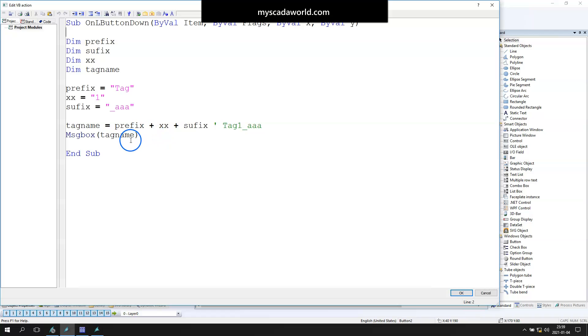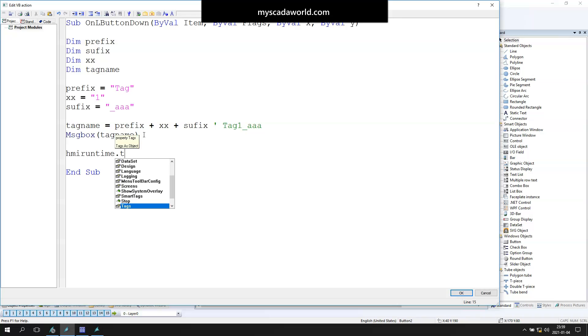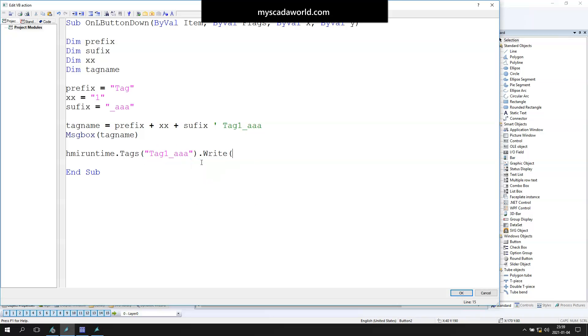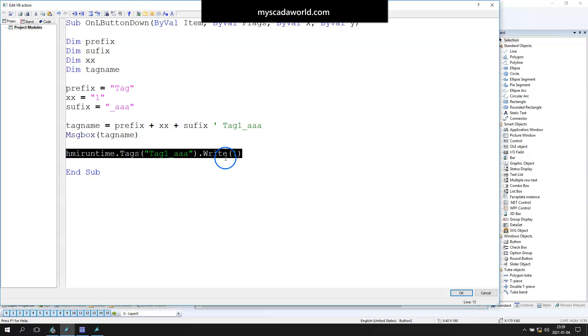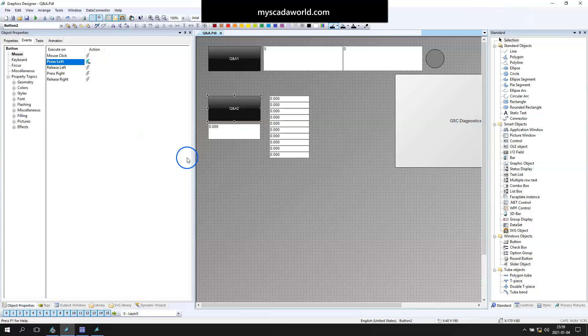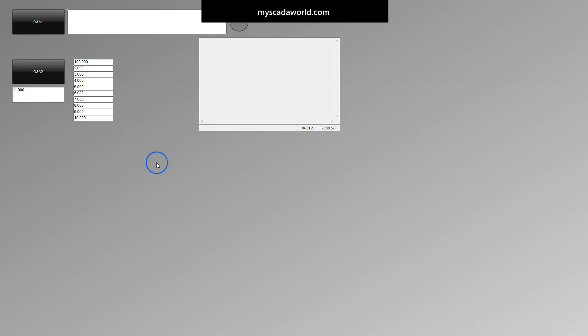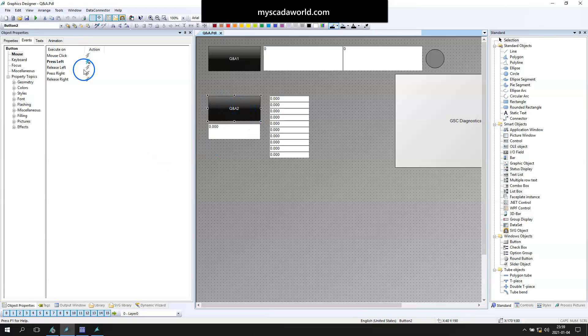Now let's open the WinCC Visual Basic script and change this script for better understanding how to write data into our final tag. So hmiruntime.Tags, and inside this we need to put tag one AAA and write data—for example, let's say 100. This line in the script should update our tag one value into 100. Let's run WinCC runtime. It's still message box the same, and our value in tag one is 100.